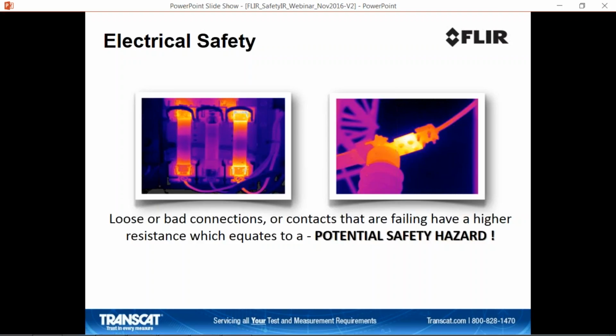Well, I got news for you—if there's a bad connection causing that problem to heat up, and you agitate that cable or wire connected to the phase, you may cause a pretty bad arc flash, or it may just arc as you open the cabinet. So you want the right PPE on and to keep a safe distance. A thermal imager allows you to stay at a safe distance, in most cases within NFPA 70E compliance.